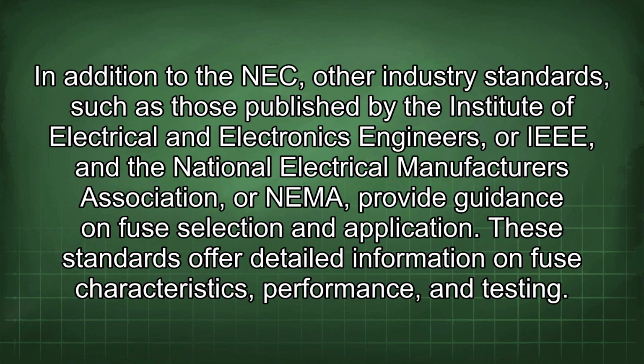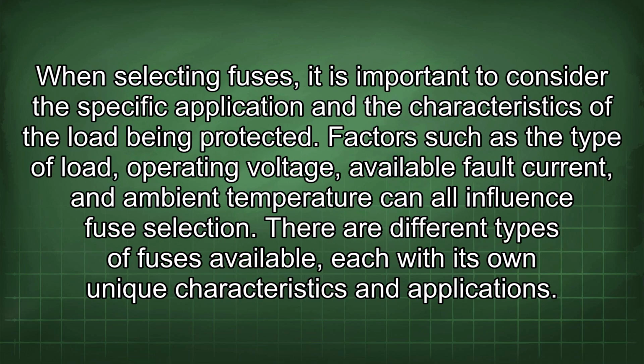In addition to the NEC, other industry standards, such as those published by the Institute of Electrical and Electronics Engineers, or IEEE, and the National Electrical Manufacturers Association, or NEMA, provide guidance on fuse selection and application. These standards offer detailed information on fuse characteristics, performance, and testing. When selecting fuses, it is important to consider the specific application and the characteristics of the load being protected. Factors such as the type of load, operating voltage, available fault current, and ambient temperature can all influence fuse selection.